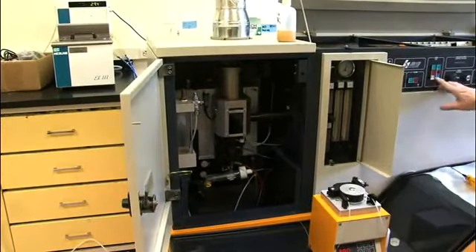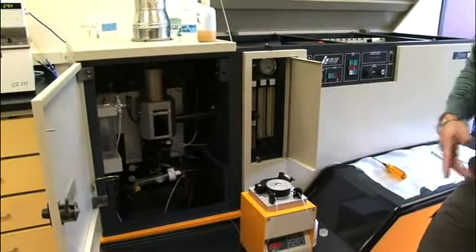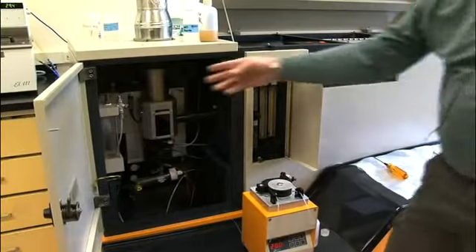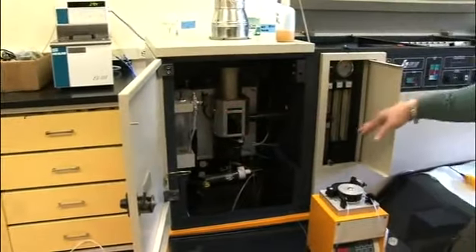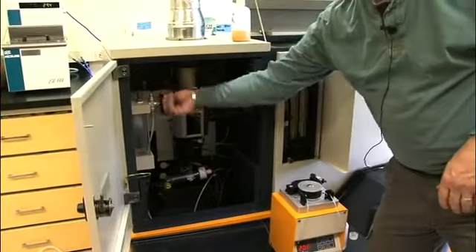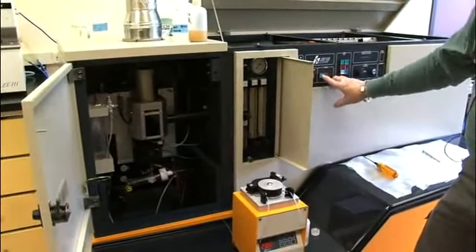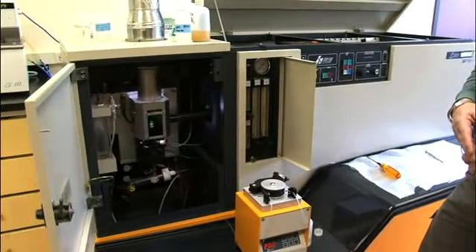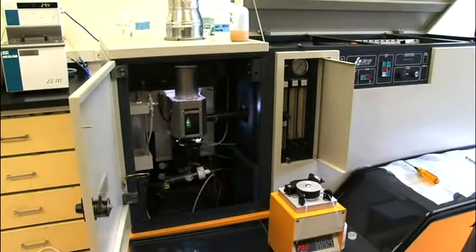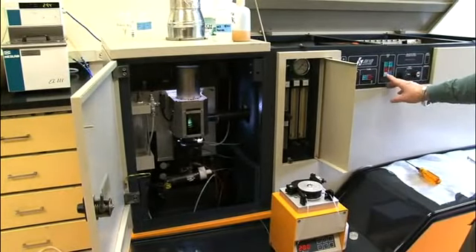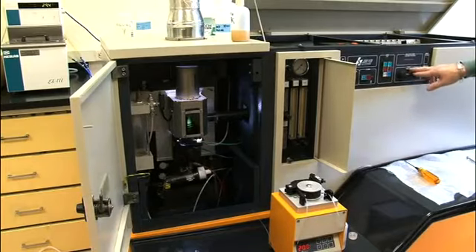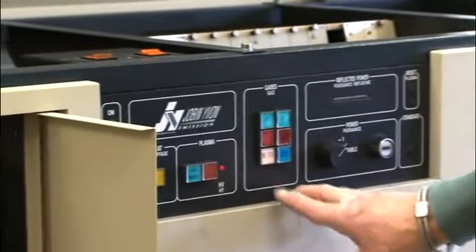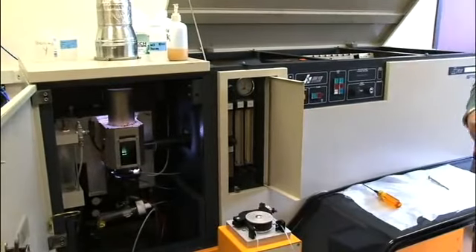Okay, so to start, we turn the neb off. Once that pressure's dropped off, and if you're using the humidifier, it's going to take longer for it to drop off. That's why you have to discharge it manually. So once that's dropped off, we click on start. You let that sit a couple of seconds. As far as power setting, you always use power 1. That should be equal to 1,000 watts. That's nominal for aqueous. And then that should be up.